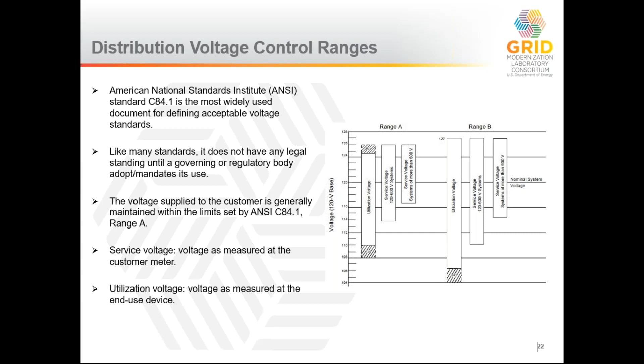Next slide, please. When you look at an operational distribution system, it is almost always maintained within the Range A limits of ANSI. The traditional way this is done is you take the voltage at the head of the distribution feeder or circuit, which is the substation, and set it at the high end of the ANSI band, typically around 125 volts. And then the voltage tends to drop as it goes down the circuit because of all of the loads on there. Now, in a system where the power all flows from the substation to the end, that makes sense. You have a consistent drop of voltage the entire time.